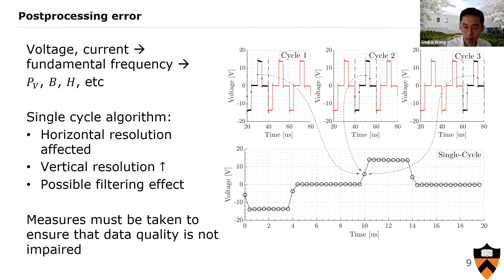Once we obtain the voltage and current waveform in the single cycle, we can calculate the instantaneous flux, which is proportional to the voltage, and H, which is directly proportional to the single cycle current that we have.